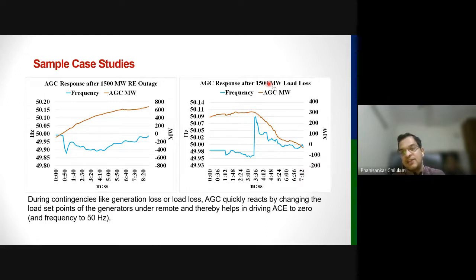Similarly, there was a 1500 megawatt load loss. An arc furnace tripped somewhere in Madhya Pradesh, and a quickly 300 megawatt ramp down was issued by AGC, like that.